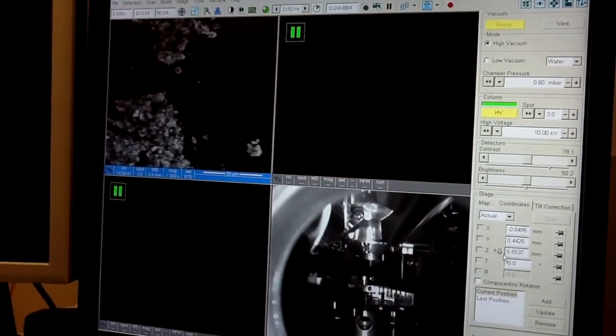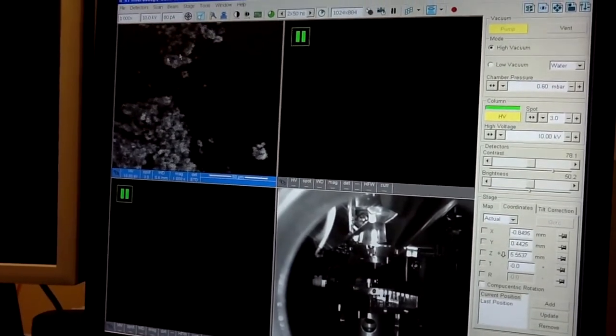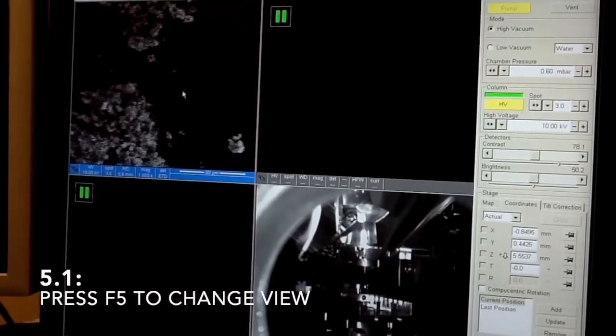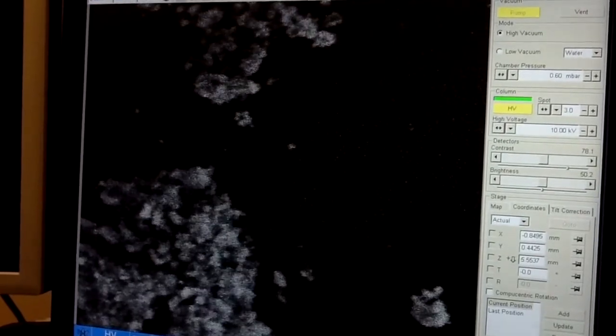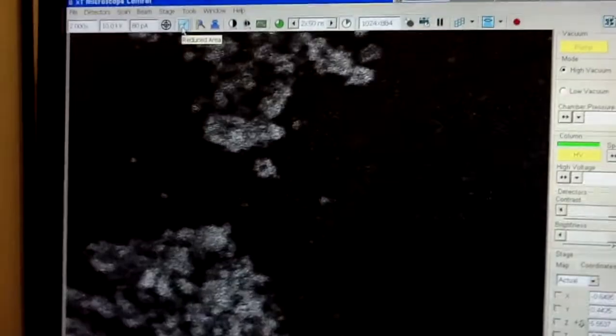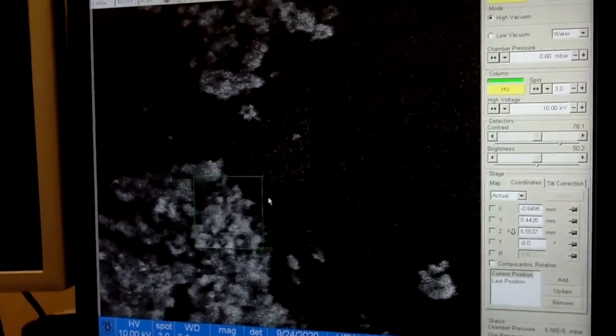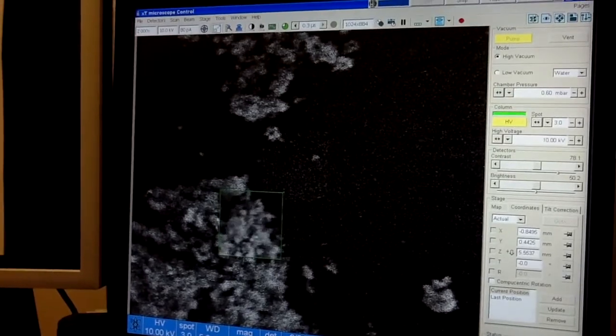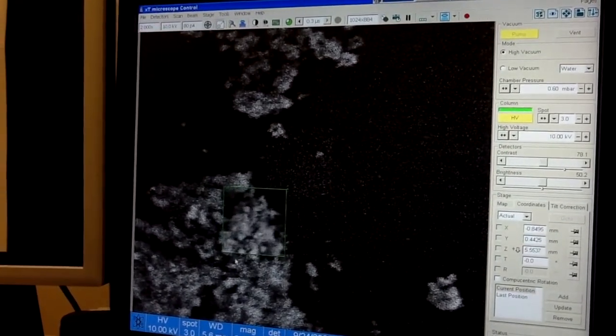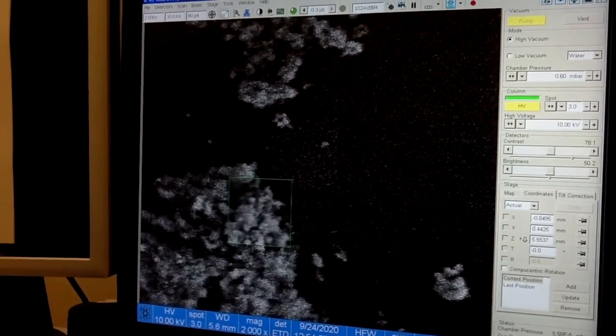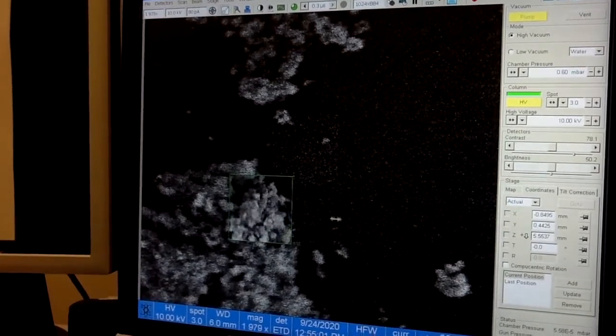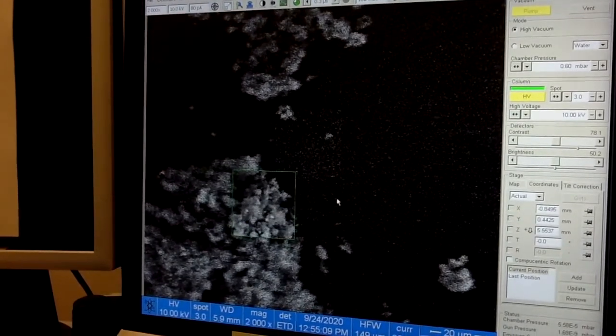After you set up your height right and you have your working distance at 5 and linked to the focal length, you can now work on getting a good image. For this, press again F5 and go to the large view. Now you can use this icon here. This tool here, which is reduced area tool. This will produce a small window and only this small window will be a live image. Which is perfect for alignment. It has a very high refresh rate, so it reacts very quickly to whatever you do. First thing you need to focus. So, again, press the right button on your mouse and just scroll to the side. And try to get the best focus possible.